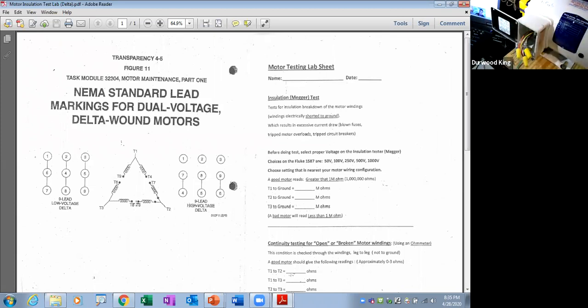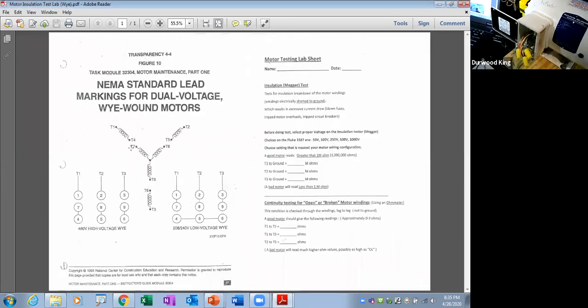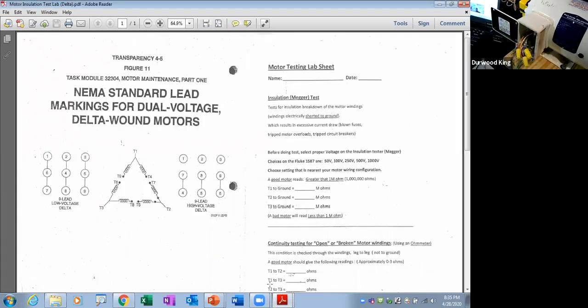Delta is the one that you don't see all that much of in some plants, but at Schindler, it's what you see predominantly. Let's just say this: delta wound motors have higher startup amps. A motor constructed like this has a higher torque on startup than a Y does. So this has a really strong startup, versus a Y wound motor, which has more of a soft start. It doesn't draw as many amps and doesn't have as much torque on startup as a delta does. So that's the primary difference.